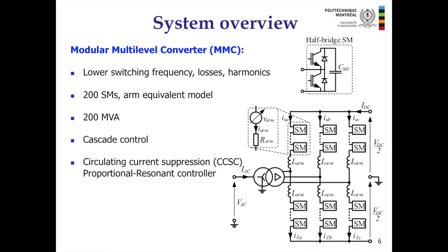As for the MMC, that is the basis for the HVDC link. The structure is shown on the right, and it is the most recent type of HVDC converter, with many benefits compared to traditional two-level or three-level converters: lower switching frequency, lower losses, and lower harmonic content. However, the structure is more complicated. In these simulations, I was using 200 sub-modules, so 201 levels, with an arm equivalent model, and the power was 200 MVA.